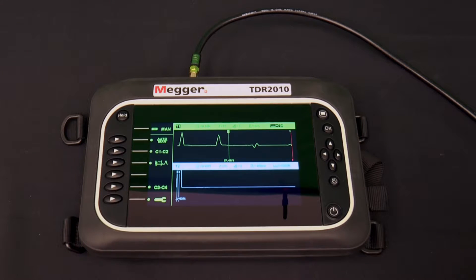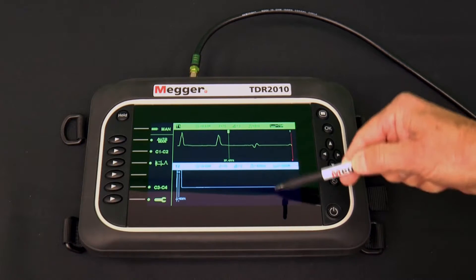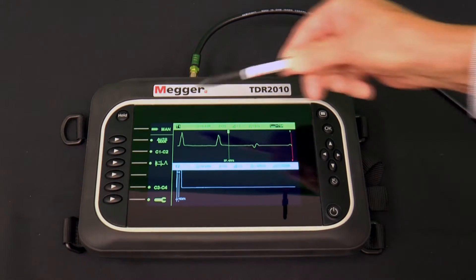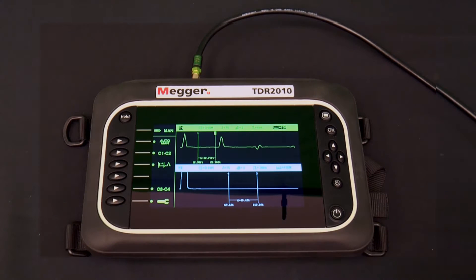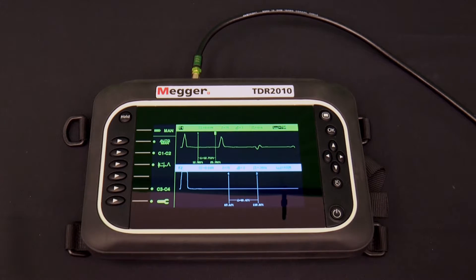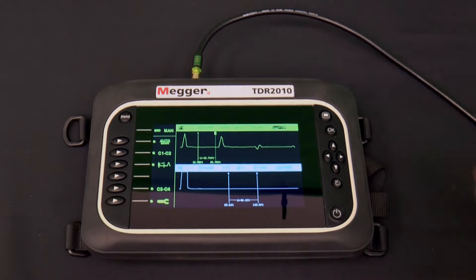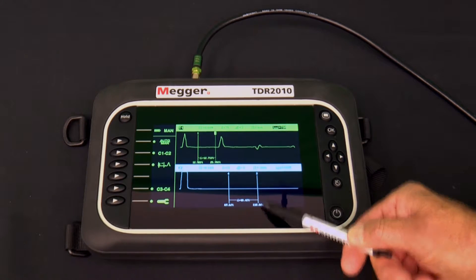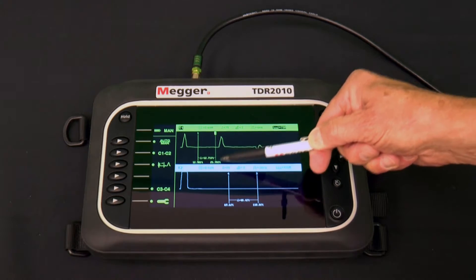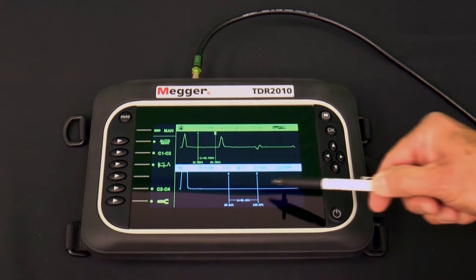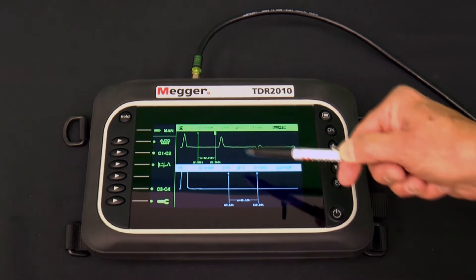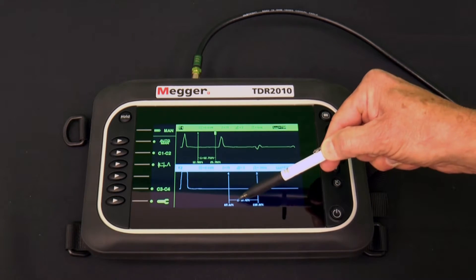Let's analyze some traces. In this case, we have two traces and we are in manual mode — MAN is displayed at the top left. It's time now to look at the cursors on the screen. Each trace has two cursors. The distance from the TDR2010 to each cursor is at the bottom of the screen under that cursor. The distance between the cursors is right next to the delta sign, the triangle.